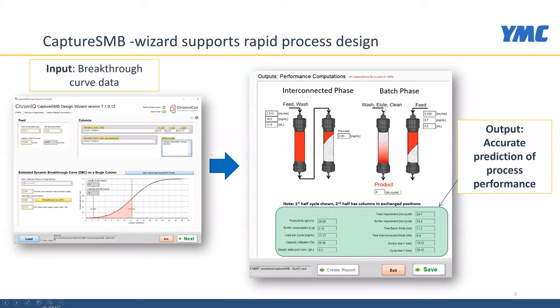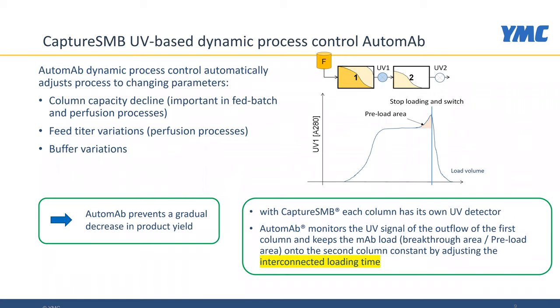There are quite a number of operating parameters that need to be defined in the Capture SMB process, which will have implications for process validation. We also want to be able to operate Capture SMB with a UV-based dynamic process control. The process control records the breakthrough signal of antibody breaking through from the first column, then stops the loading once a certain threshold area under the breakthrough curve is reached. This UV-based control feature is called AutoMab.